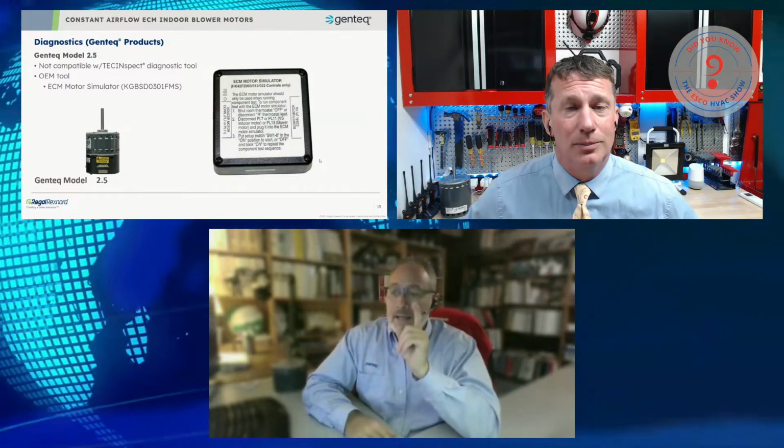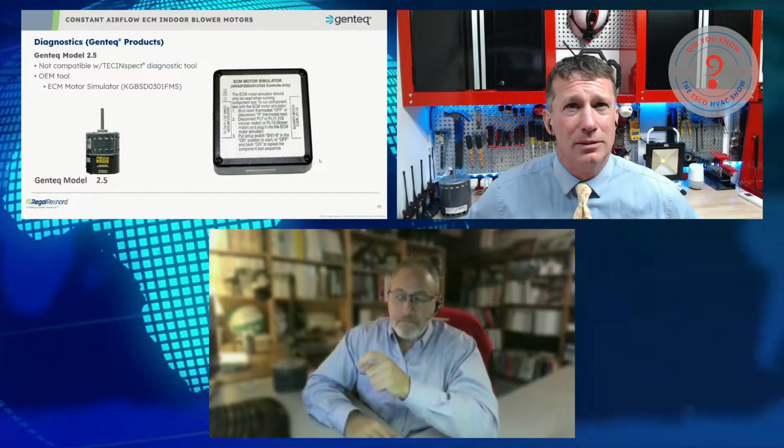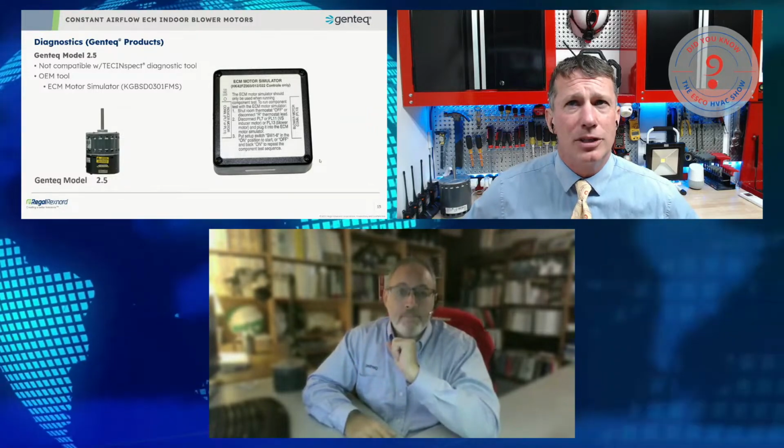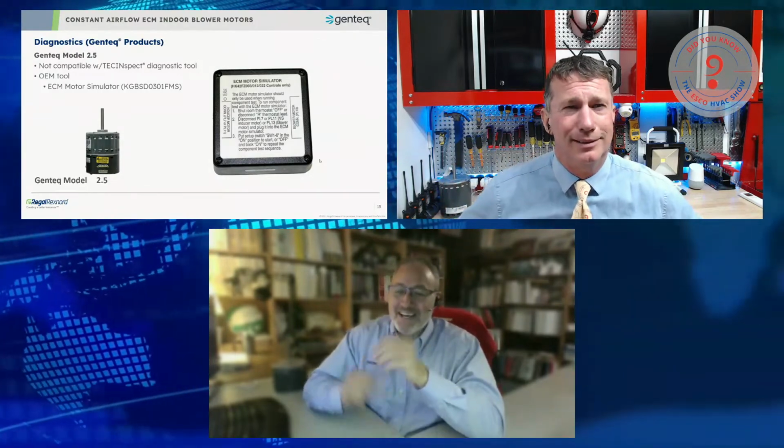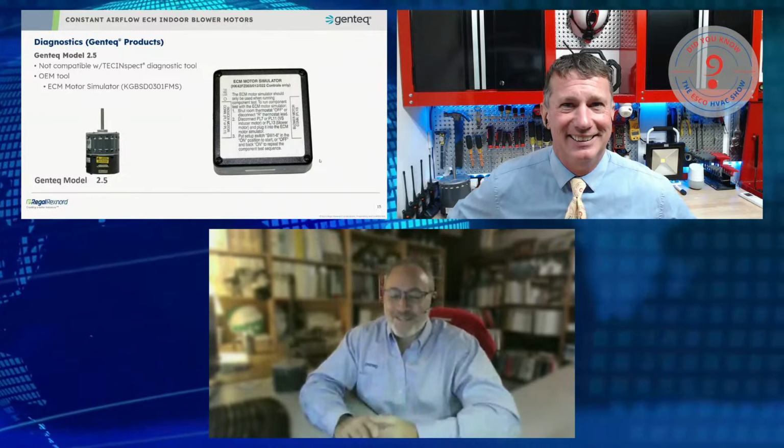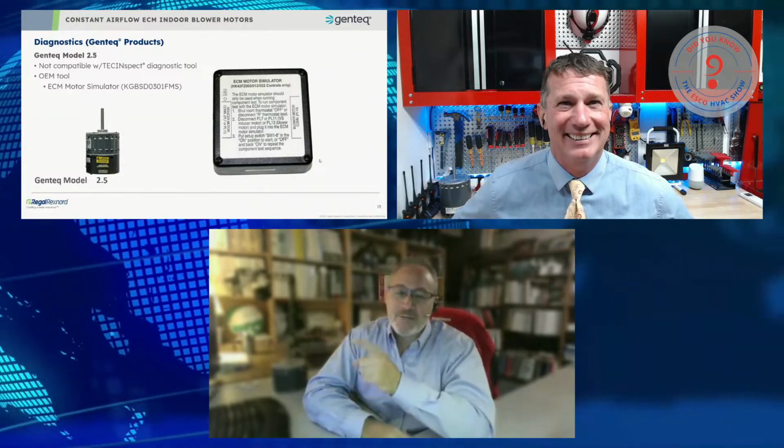Yeah, absolutely do. And those were a 16-pin also, weren't they? Or close to that? They were actually a 9-pin. I remember the harness, I just don't remember how many wires were in it. But it was a lot of wires. It's a draft blower, why are there 9 wires going to it? But this box will actually diagnose those draft blowers as well.